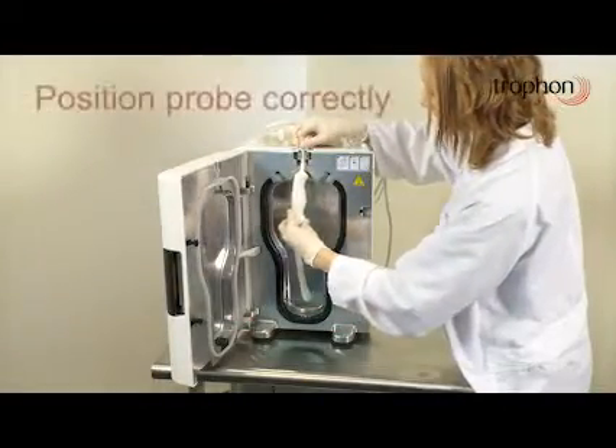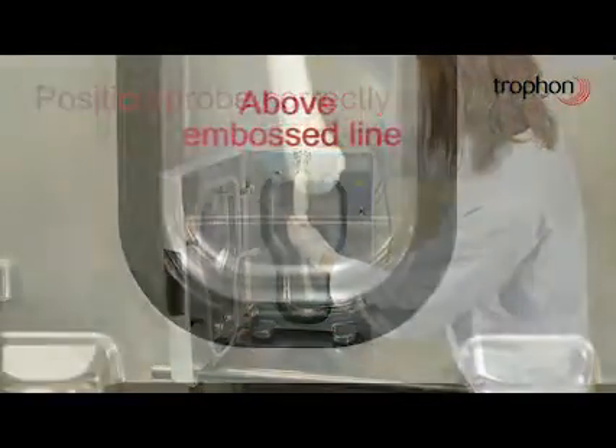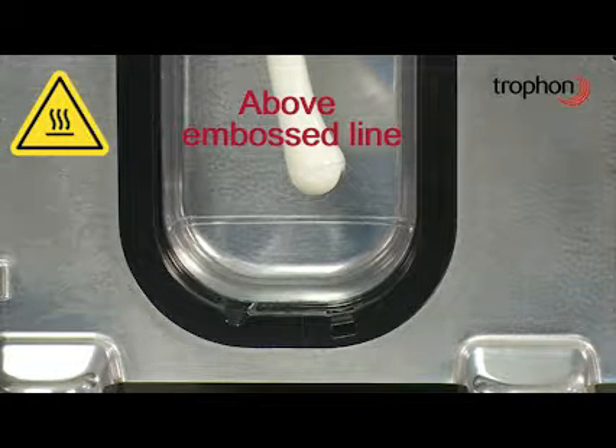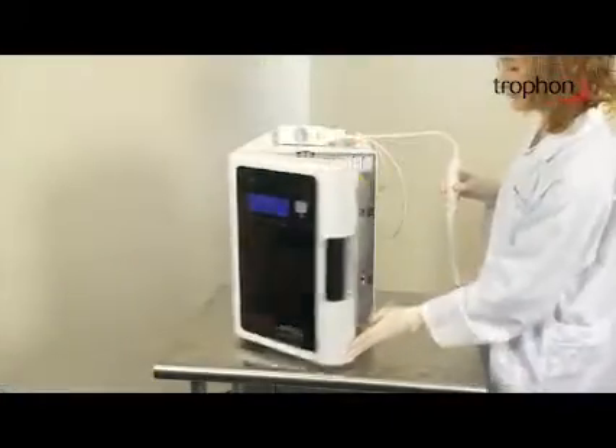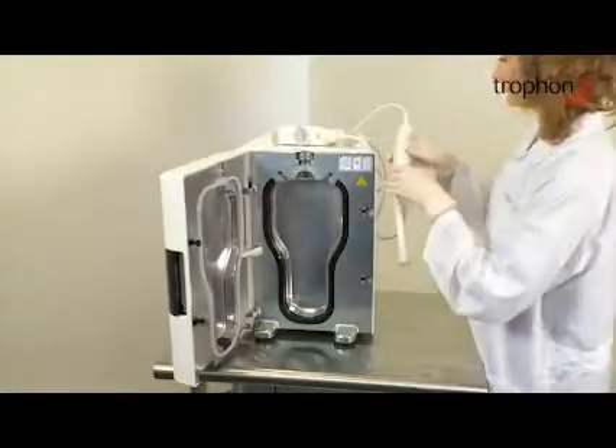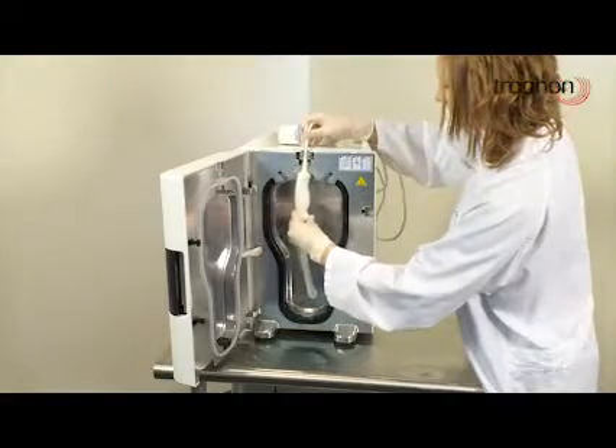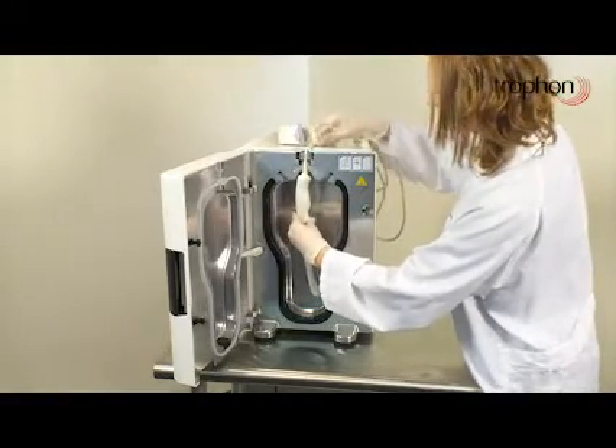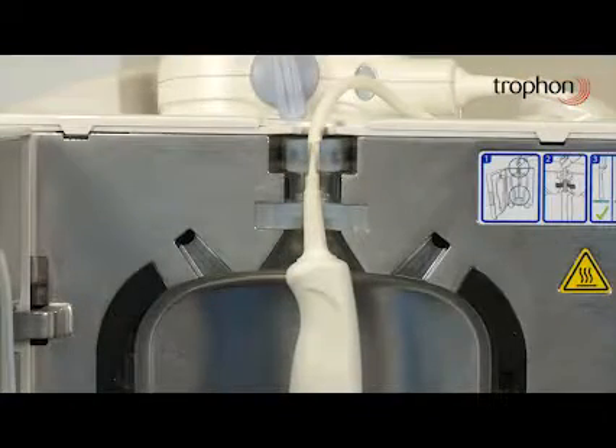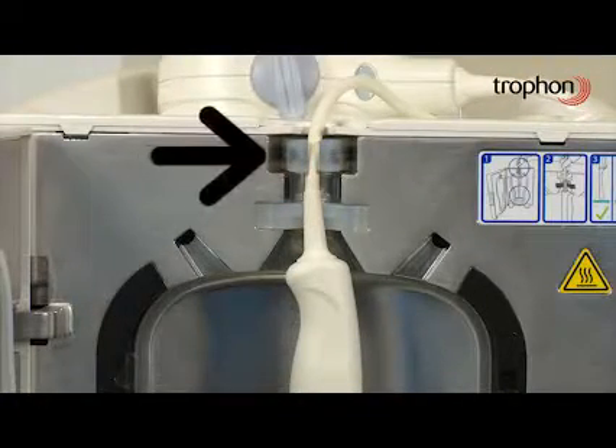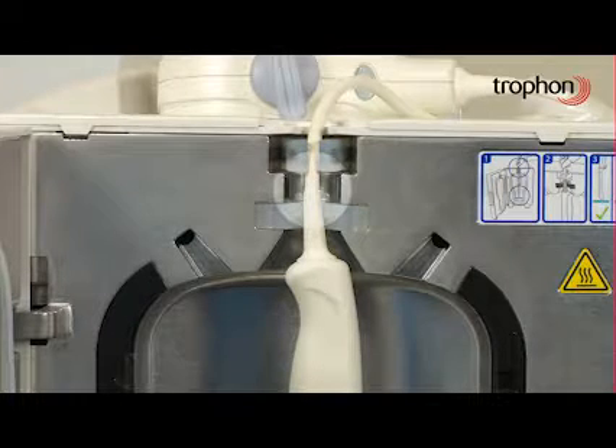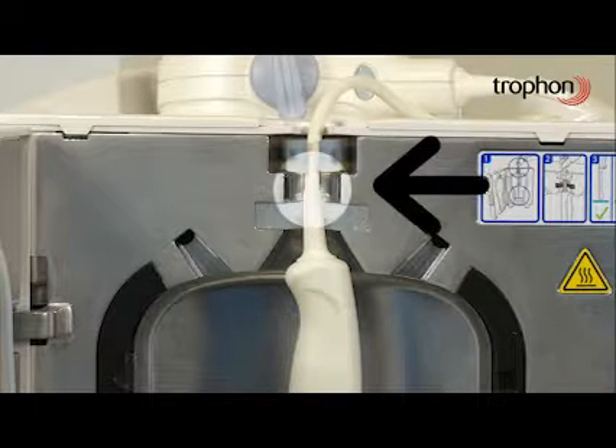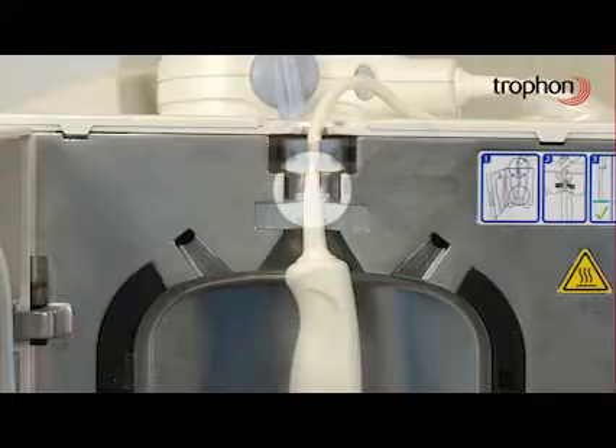It is important to position the probe correctly. Place the probe in the disinfection chamber above the embossed line. The chamber wall is hot and should not make contact with your hands for an extended period. Ensure that the probe does not make contact with the chamber wall. The cable of the probe should be securely positioned within the clamp. Ensure the top of the probe's cable gland is above the seal.